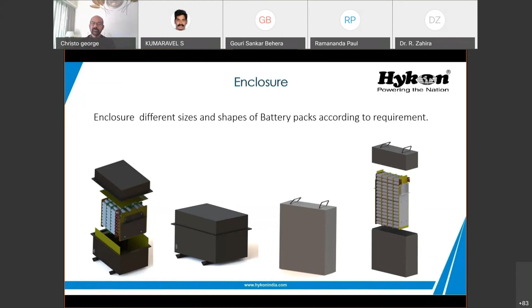Next, battery cooling. LFP doesn't require cooling, but at most you can give air cooling, which is more than sufficient if needed. High current discharge applications get air cooling. Normal LFP batteries are not provided with cooling because they don't require it. But for some battery chemistries, cooling is critical, so the enclosure has to be designed with either natural cooling or forced cooling.